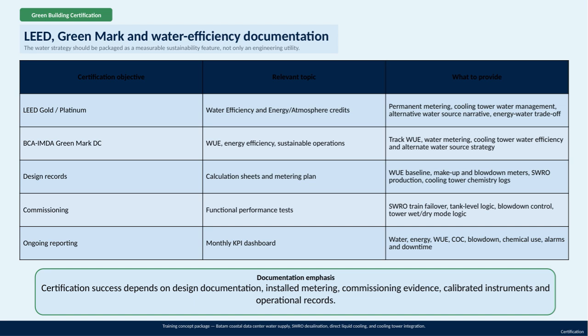Looking at certification objectives, LEED Gold and Platinum prioritize water efficiency alongside energy and atmosphere credits. To achieve this, permanent metering, cooling tower water management, narratives on alternative water sources, and understanding energy-water trade-offs are essential. For BCA-IMDA Green Mark certification, tracking water use efficiency, water metering, and sustainable operation strategies are critical. Design records must include detailed calculation sheets and metering plans, establishing baselines for water use efficiency, and documenting meter data for makeup water, blowdown, SWRO production, and cooling tower chemistry.